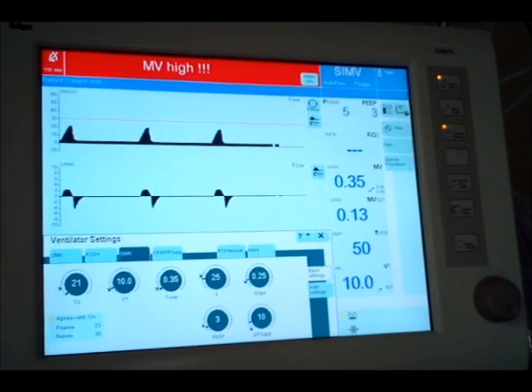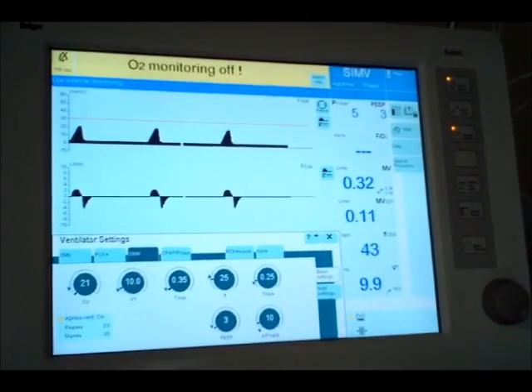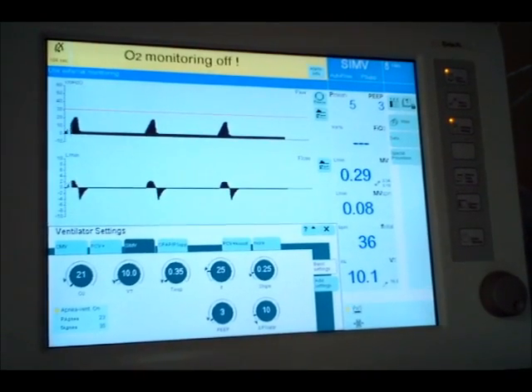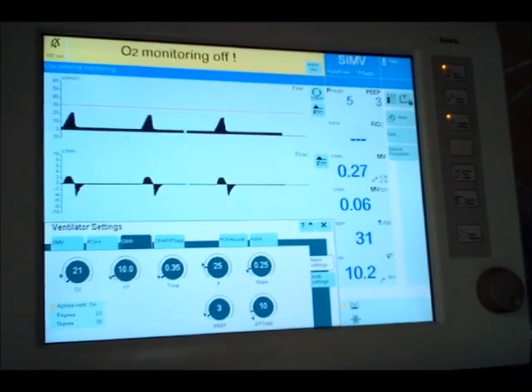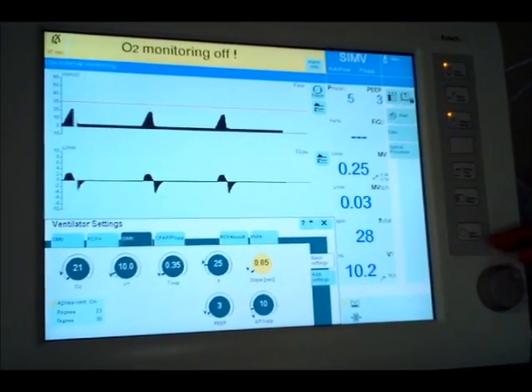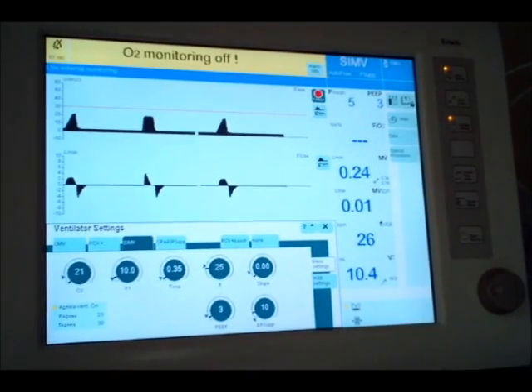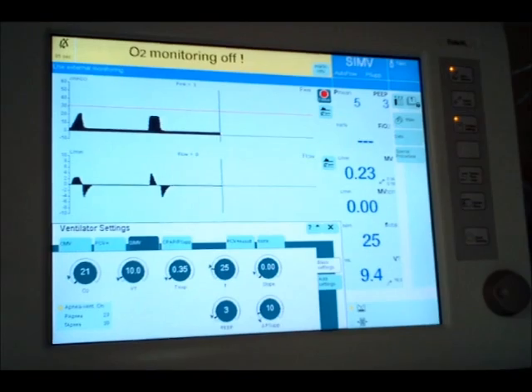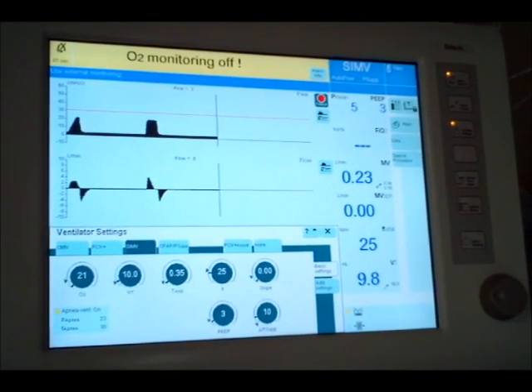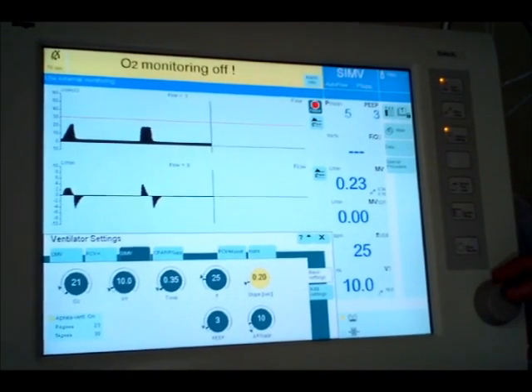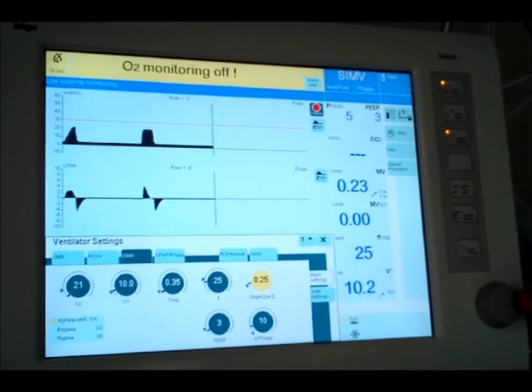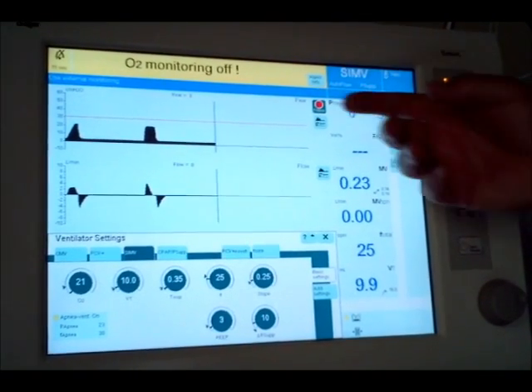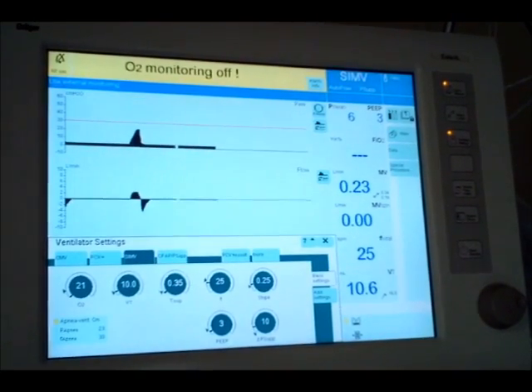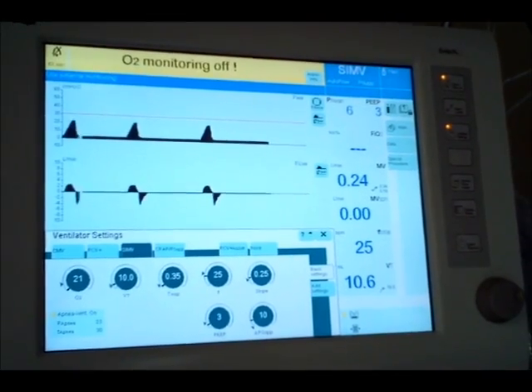Okay, again, making the change isn't that hard. The slope will apply to both the mechanical breaths and the pressure supported breaths. Typically, a slope of 0 would do what? Okay. So, to give you a good comparison, there's a slope of 0.25. There's a slope of 0. Which one do you think the baby's more comfortable breathing with? Probably having a little bit of slope. So again, with the Babylog, we did that with our inspiratory time. Here we have an actual control where we can change that. And that's not going to be something that's going to be ordered. Your slope is going to be up to you. Sensitivity will be up to you.